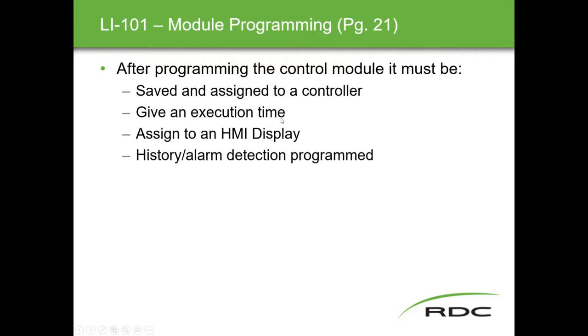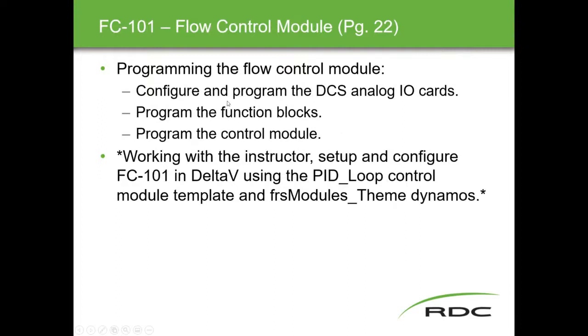Then give the module an execution time — how often you want it to gather information and execute. Assign that information possibly to an HMI display so the operator can see temperature, level, or flow on a bar graph or numeric display. Also program history and alarm detection, tying that transmitter's address to the alarm database or historian database server that stores all that information.